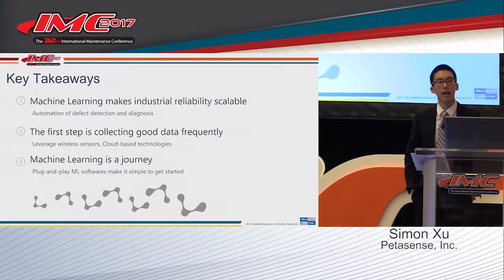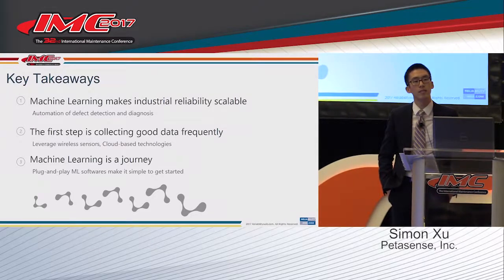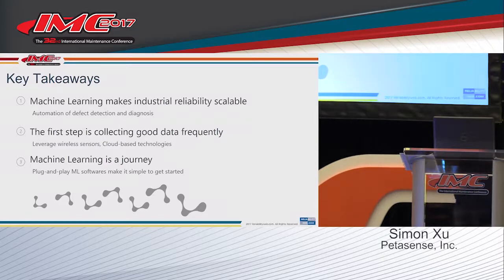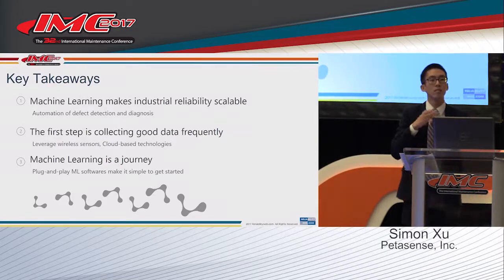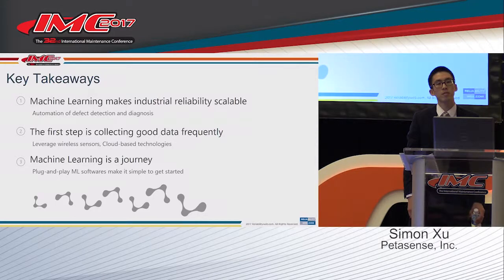Hello, I'm Preston Johnson with Allied Reliability Group. I'm a platform lead in intelligent monitoring. From a vibration analyst perspective, which I've had some training there, I would look at a number of vibration sensors on something like a motor pump. I would calculate 10 or 15 condition indicators off of each one of those sensors, and then I'd be looking for some combination. I probably have 150 or so features. If I'm getting started, can you just start feeding data in, call it normal, and then machine learning will find an anomaly that I can then go identify? Is that a reasonable approach?